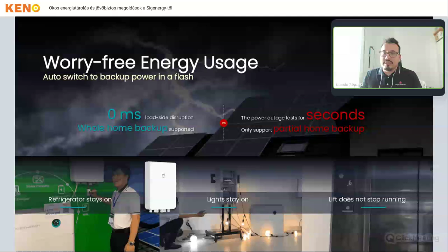Granular management, what is the meaning? As I have said, so far in most of the scenarios, batteries were connected in series just to increase the voltage, and there was one BMS, as a battery management system. And in the case of such products, every time you're willing to connect new batteries, there must be some pre-charging scenario. This is very similar to PV modules, where optimizers are demanded because shaded modules work differently. In that case it's very similar. Different batteries can have different states of charge, and there has to be some process to pre-charge. So there is some kind of leak of capacity in the system, and it cannot work fully. We cannot utilize the full capacity of the system.